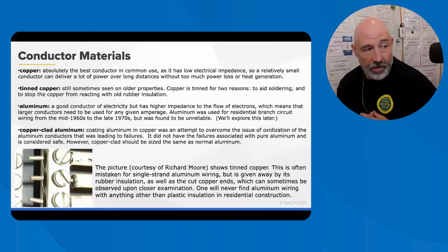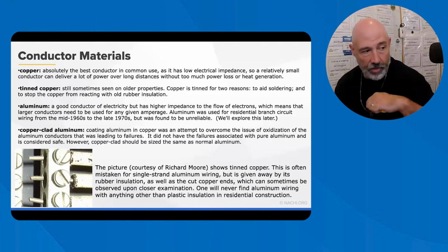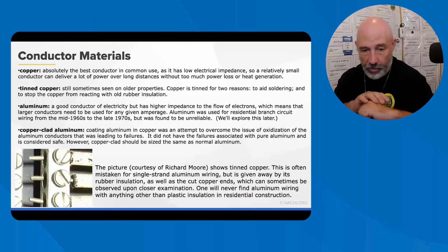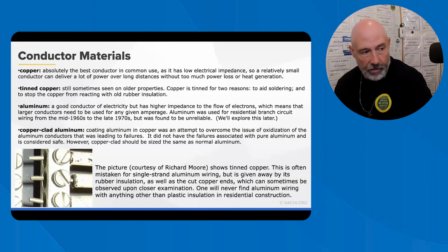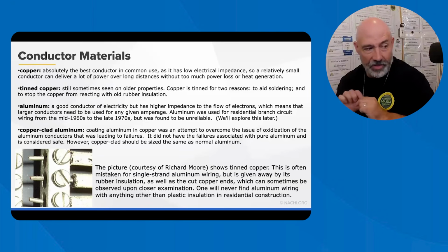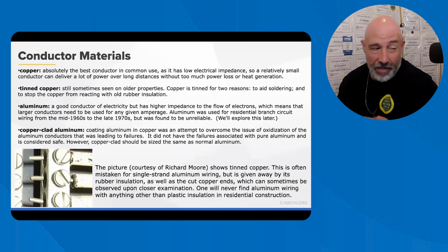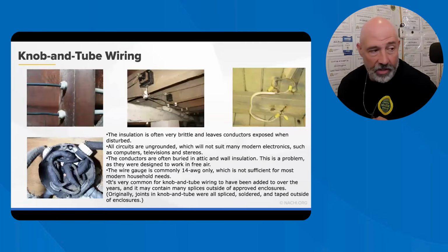Conductor materials here. Again, copper, you've got the tin copper, you've got the aluminum, you've got the copper clad. Basically what that is, is aluminum with copper sheathing over it, and they've had pretty well success with that. But it does have some oxidization to it, so it should have that lubrication on there, and that's the biggest thing with aluminum wiring.